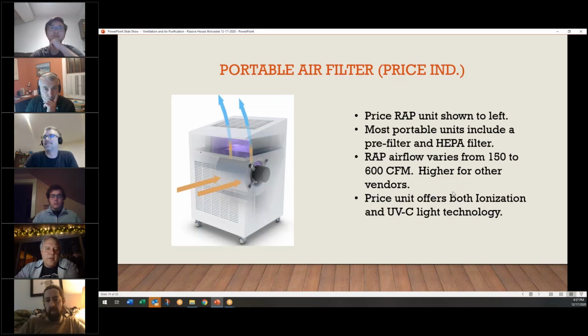Okay, so portable air filters have been very widely used in the classroom environment to try and get these schools to reopen. Price Industries makes this. They call it a room air purifier. Basically, it's just a HEPA and a fan. It stands in the room, brings air in through a HEPA filter, and blows it out. The only difference with this is they do offer ionization. They have a needle point ionizer in there, and they also offer UVC light. So you can actually have all three technologies if you want.